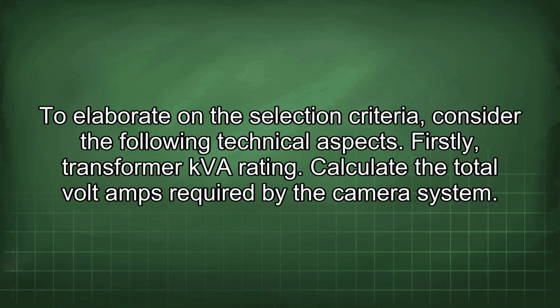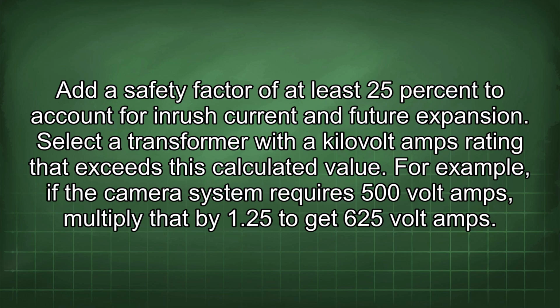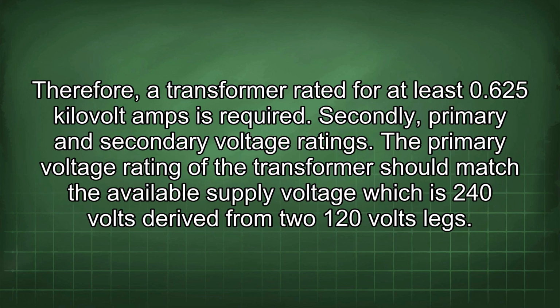Firstly, transformer kVA rating. Calculate the total volt-amps required by the camera system. Add a safety factor of at least 25% to account for inrush current and future expansion. Select a transformer with a kilovolt amps rating that exceeds this calculated value. For example, if the camera system requires 500 volt amps, multiply that by 1.25 to get 625 volt amps. Therefore, a transformer rated for at least 0.625 kilovolt amps is required.